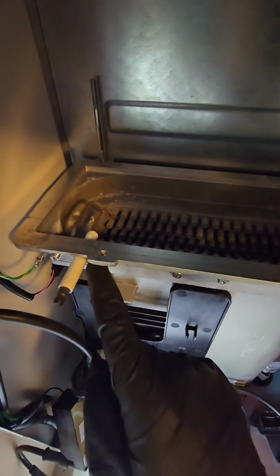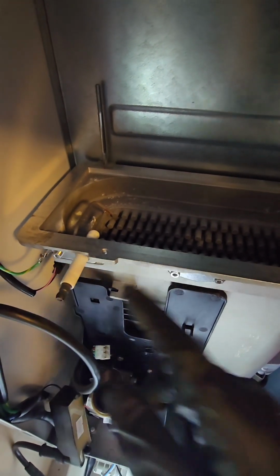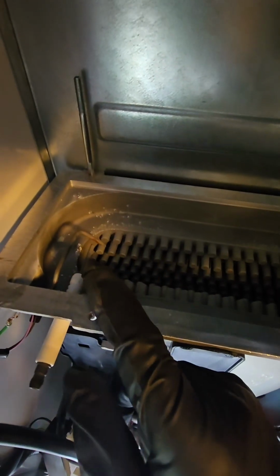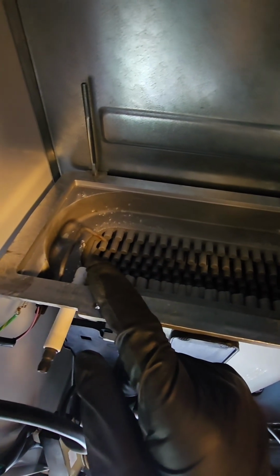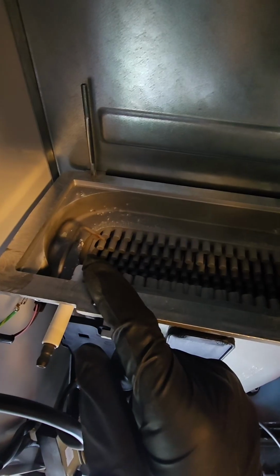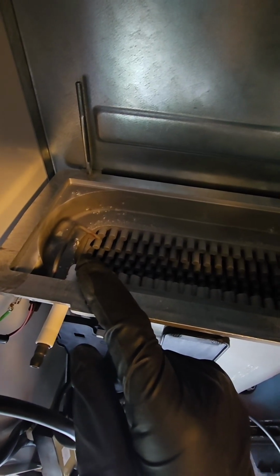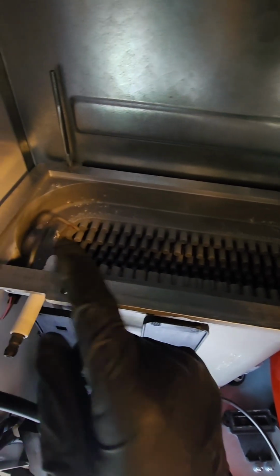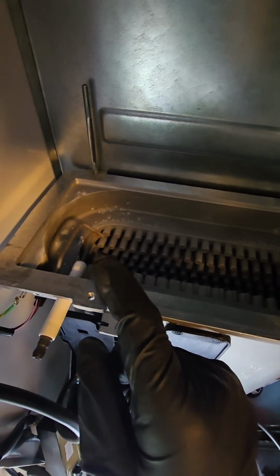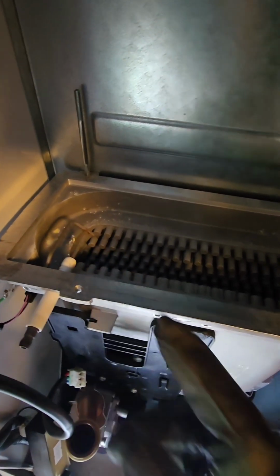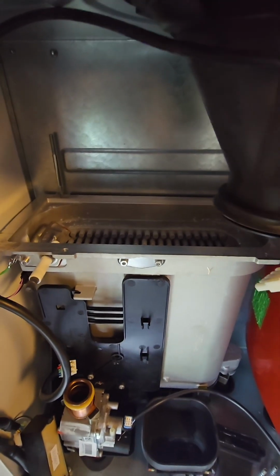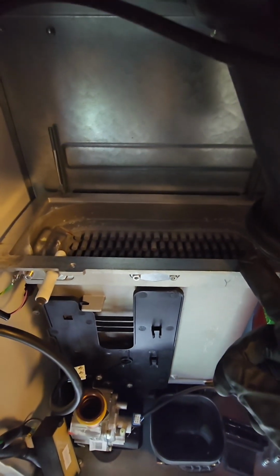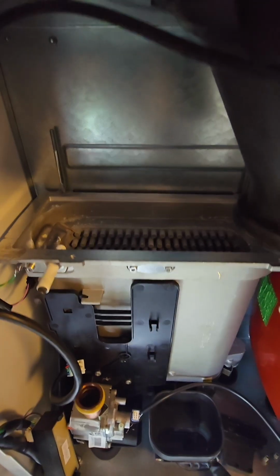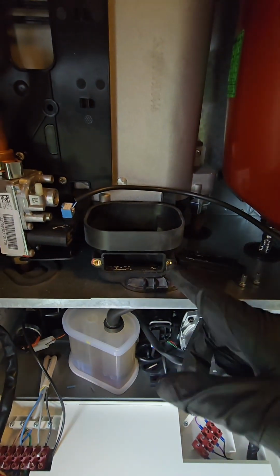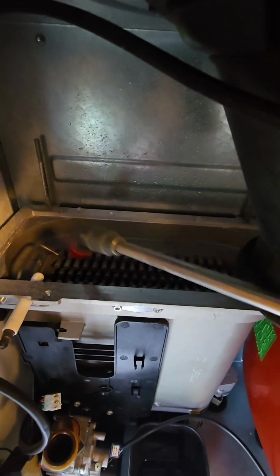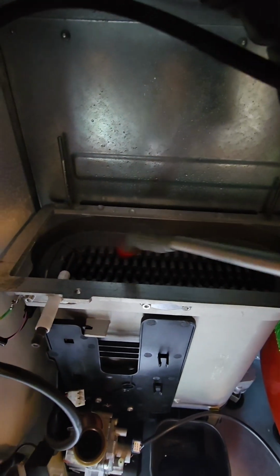Using an Allen key, remove the electrodes. These ones aren't too bad, however we're going to clean them anyway, using either wire wool, or if they're particularly bad we would use a file. If they look overly worn, then obviously we would be replacing them. For the next part we're going to wash through the heat exchanger. Before we do, we need to replace the sump cover. So now we're going to wash through the heat exchanger with a pressure washer.